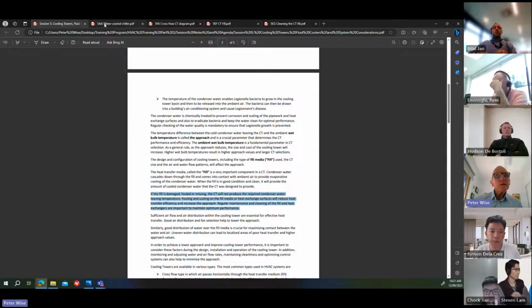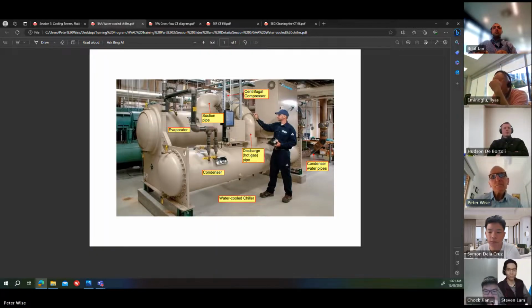And speaking of fouling, in the condenser tubes of the water-cooled chiller or any other heat exchanger that has condenser water going through it, it's important to have a regular cleaning regime. With the chiller, it's every 12 months. They'll come in, take the ends off the chiller and clean the tubes out, because you'll get this build-up of scale, which affects the performance. I'll close that.